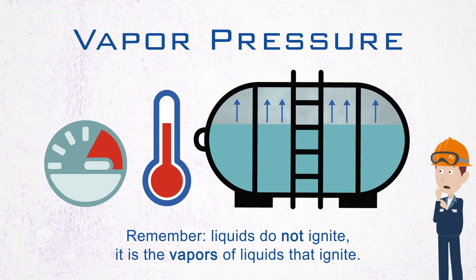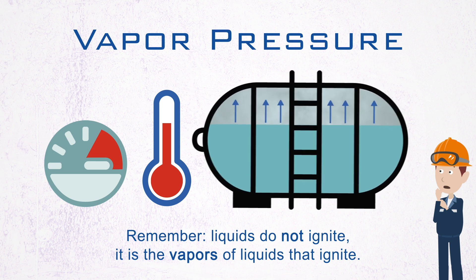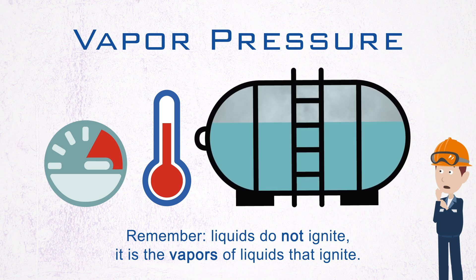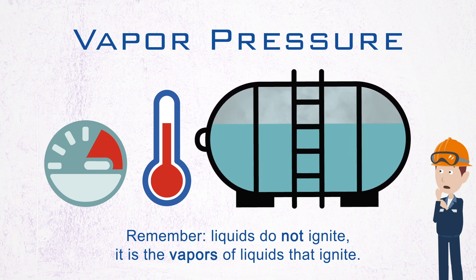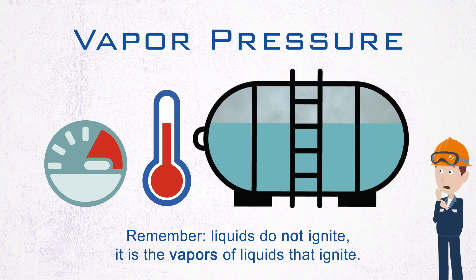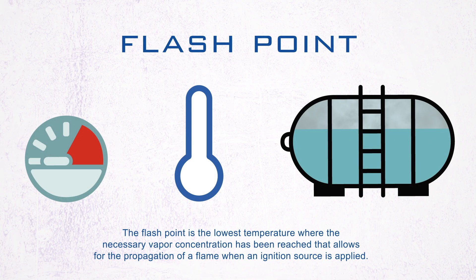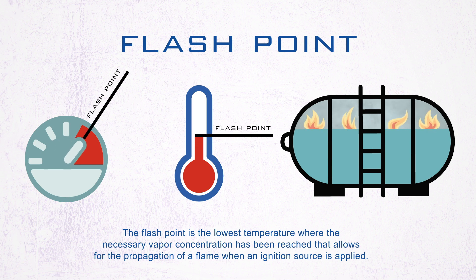Remember, liquids do not ignite — it's the vapors of liquids that ignite. The threshold where a material becomes a flammable hazard is the flashpoint. The flashpoint is the lowest temperature where the necessary vapor concentration has been reached that allows for the propagation of a flame when an ignition source is applied.